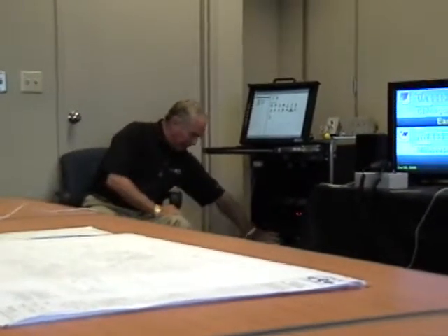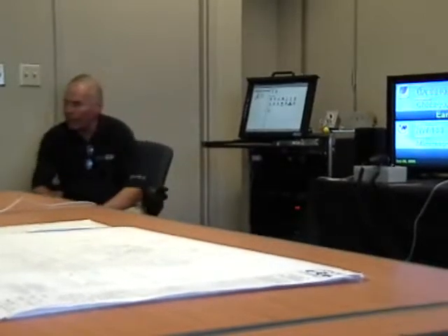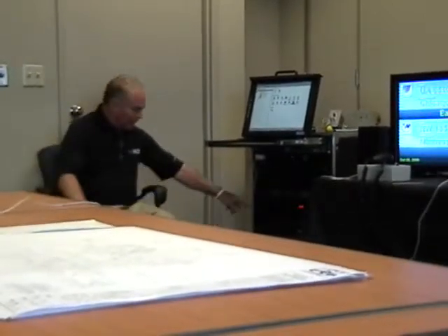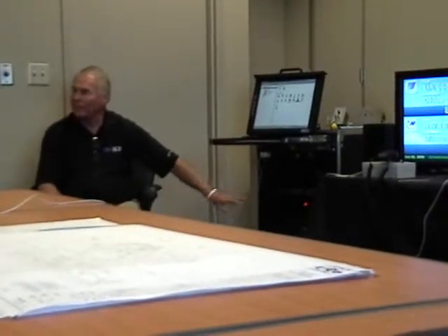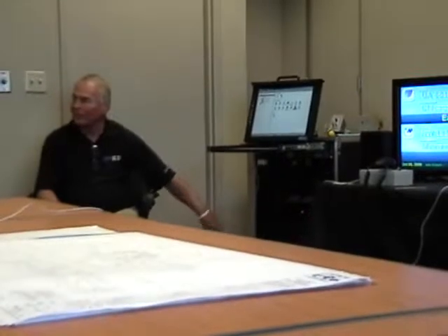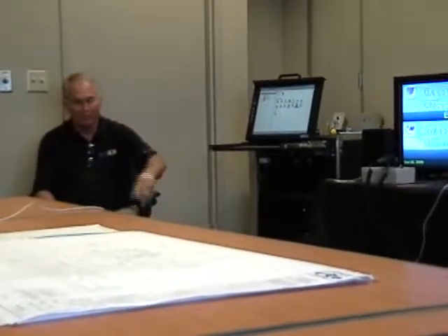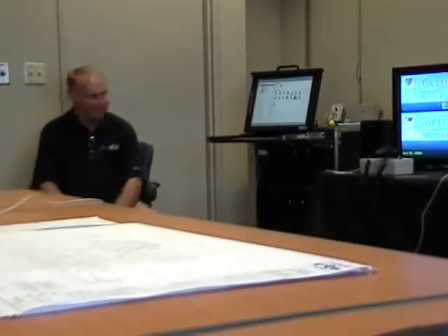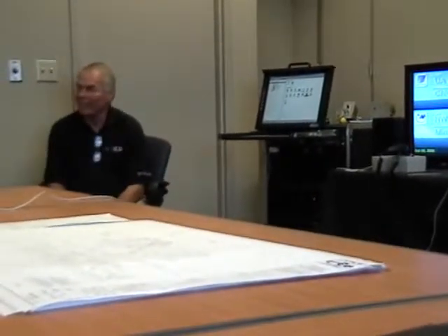And the power amplifier section is this here. This is each 200 watt channels. There's 8 amplifiers and a backup. Each one of them are dual 200 watts. So you got 16 channels of amplifiers, equalization, ambient noise, all that stuff's all in one frame. And the only wires out of the back are the speaker wires and one network cable. So that takes you all the way through what you have now.